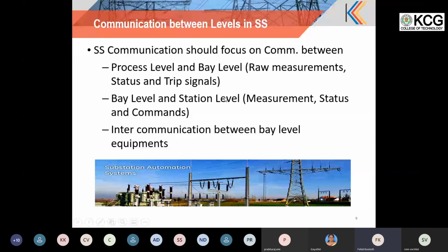Then intercommunication between multiple bay level equipments. The key scenario here is that there can be multiple IEDs, or intelligent electronic devices, which we also call relays. Each relay will have a specific function. Some will be over voltage protection, over current protection, frequency protection. So a lot of functions can be there in the multiple IEDs in the bay level. This can be a distributed function, that is, one device performs one function and its outputs are needed by another device to perform trips and other signals. So there needs to be intercommunication between different equipments in the bay level, that is, between multiple IEDs.